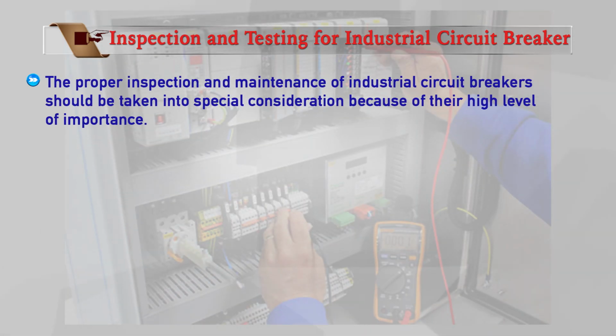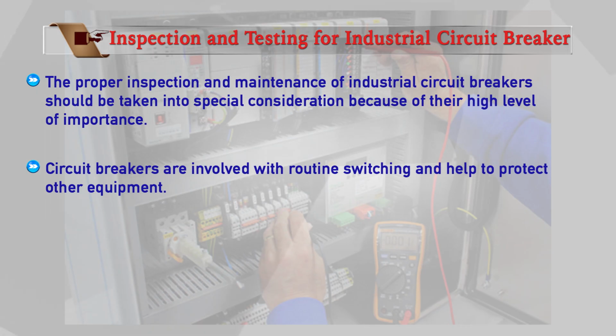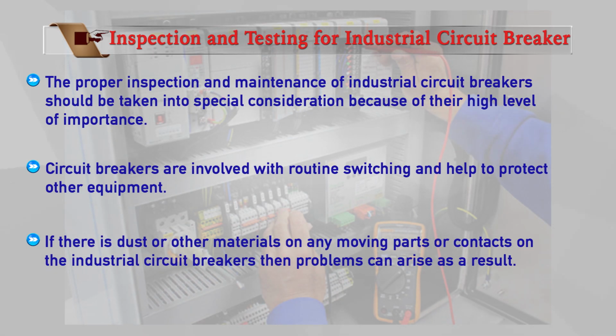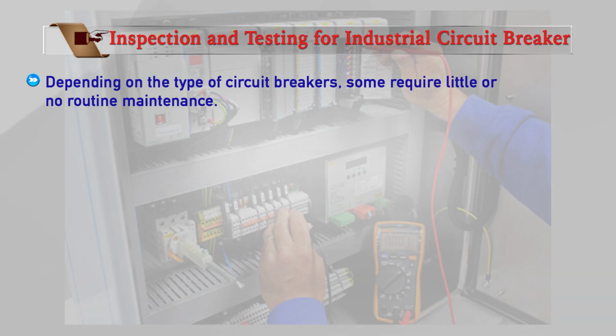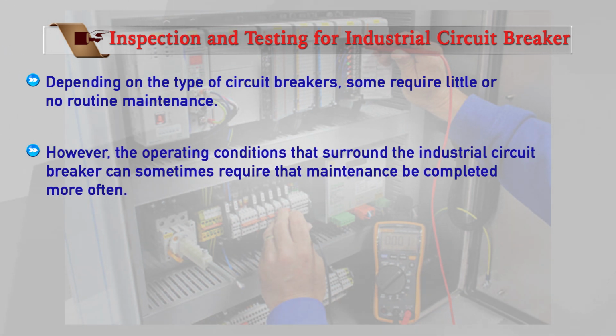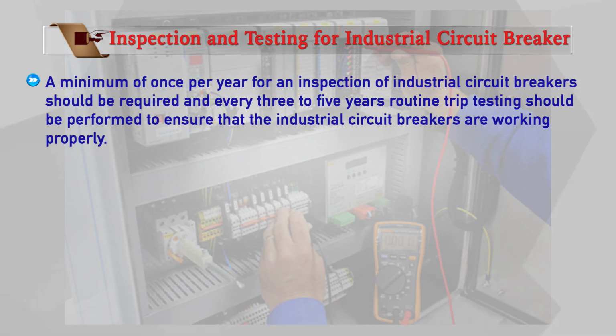The proper inspection and maintenance of industrial circuit breakers should be given special consideration because of their high level of importance. Circuit breakers are involved with routine switching and help to protect other equipment. If there is dust or other material on any moving part or contact on the industrial circuit breaker, then problems can arise as a result. Depending on the type of circuit breaker, some require little or no routine maintenance. However, the operating conditions that surround the industrial circuit breaker can sometimes require that maintenance be completed more often. An inspection of the industrial circuit breaker should be required a minimum of once per year, and every 3 to 5 years routine trip testing should be performed to ensure that industrial circuit breakers are working properly.